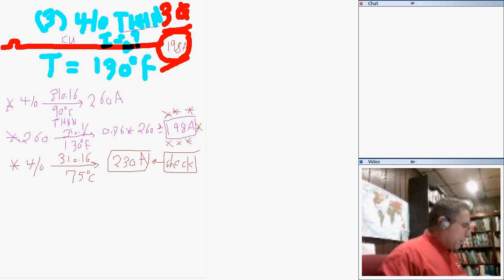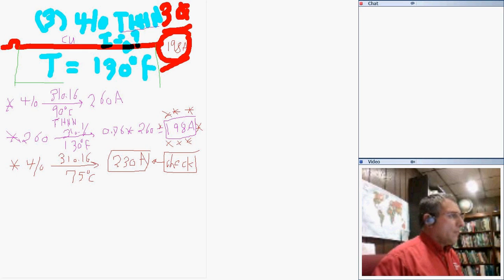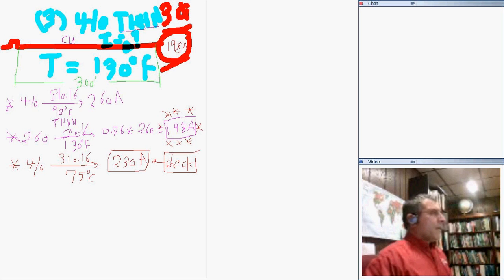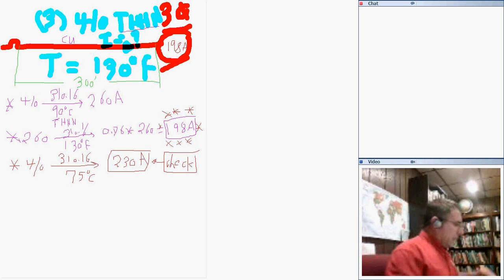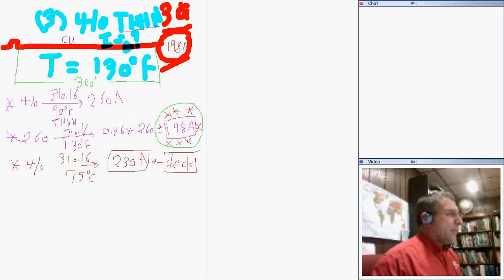Now I'll make it more interesting, and add a voltage drop calculation to the same problem. Suppose from here to here this was 300 feet of conductor. I need to size for the voltage drop. Remember, the first amps we came up with is 198. I need to see how much current I can take out of this conductor under these circumstances.